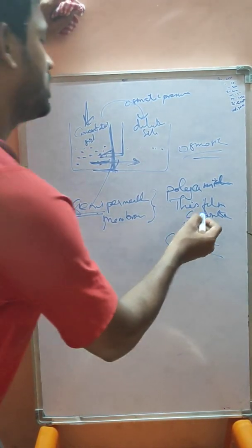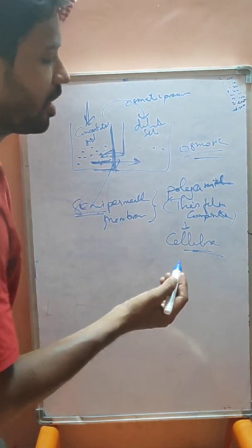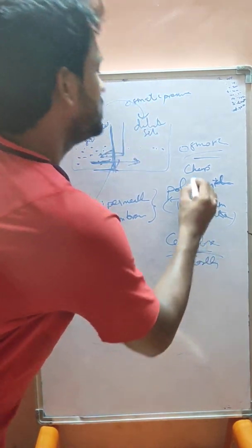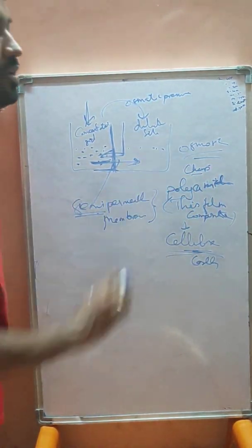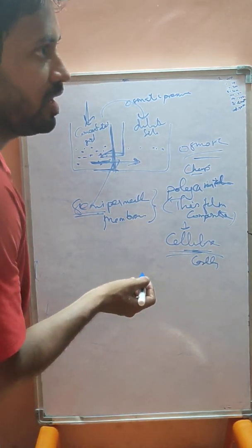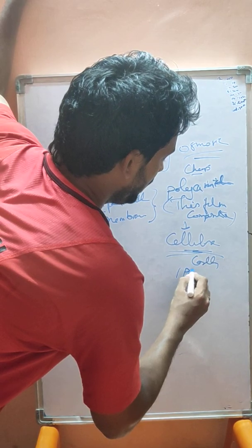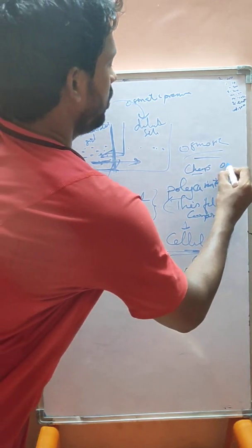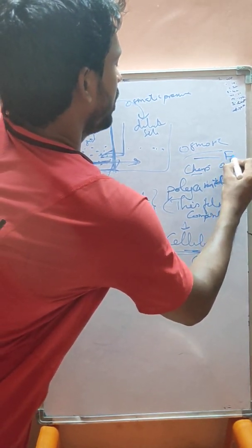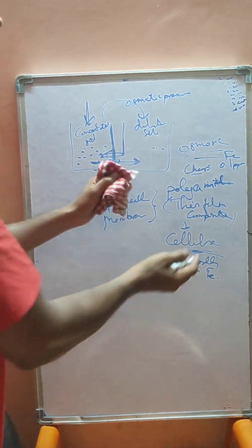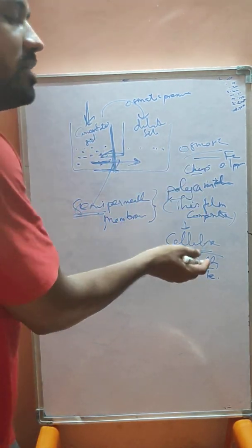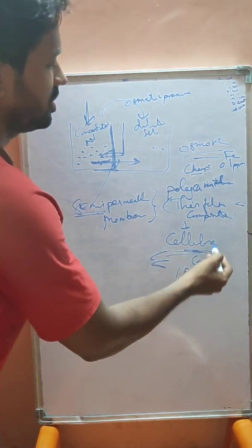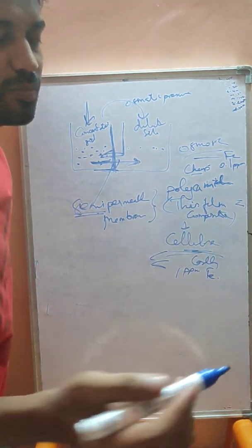Compared to polyamide, cellulose is less costly. Cellulose will allow up to 1 ppm of iron content, but polyamide allows only 0.1 ppm. There are many differences between polyamide and cellulose, such as pressure handling, maintenance, and life. You can get more data on the website.